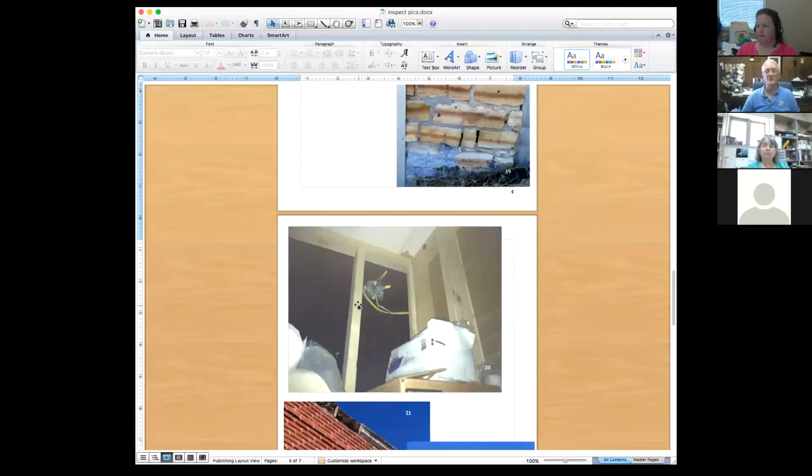This is an electrical hazard. This was in a closet, and evidently somebody did some wiring and didn't bother to tuck the wires back in and put a plate on this. A junction box is there to keep bad connections from getting hot, and if they get hot, if it's done properly, any kind of heat or sparking isn't going to catch wood on fire. So we need to look for things that are not done properly. In any building, even your home, you shouldn't have this.